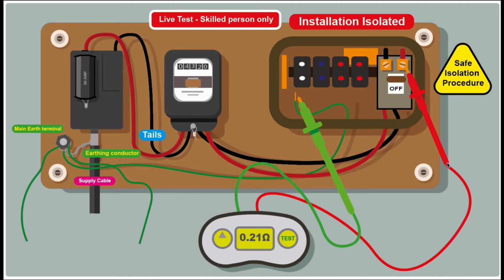Okay, so we've opened the fuse board up. We want to do our ZE test. We've followed all the safe isolation procedure, we won't go through that. And we test between the line and the earth. Now this is the conductor that goes to the main earthing terminal.